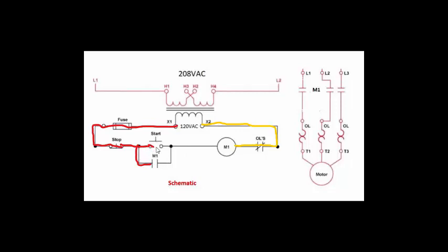Once we close the start button, voltage would then go all the way to the coil. And once this coil is energized, that will close these contacts, allowing current to go to the motor through all three phases. It also closes this auxiliary contact. And the reason for this auxiliary contact is so that when we let go of the start push button, the current will still have a path to go to the coil, and these contacts still stay closed, and the motor still runs.